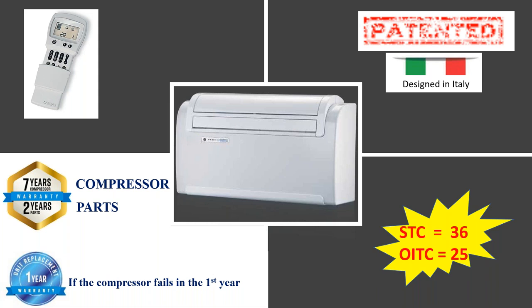Nobody's going to come in and say, well, how about, because nobody can meet the design criteria of this unit in terms of how it mounts and how quiet it is. So my guess is, having worked for a manufacturer in the past, and I've worked on any number of unit designs from cradle to grave, I know that to develop a unit like this would take any manufacturer a minimum of 2.5 to 3 years. That's assuming they don't take any shortcuts. Anybody that tries to design from scratch and produce a unit in less time than that usually regrets it in more ways than one.